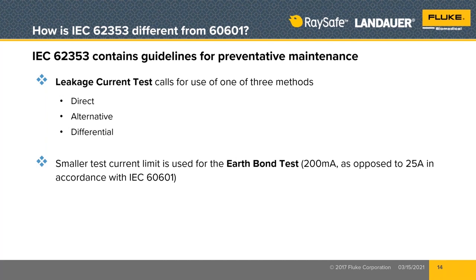Now, the test instrument that we're going to show you today, the ESA 615 electrical safety analyzer, can only do 200 milliamperes of testing. So we're going to do this testing today as if we were using the ESA 615 and we were doing it the way you would be using it in your biomedical department or in your field service organization.